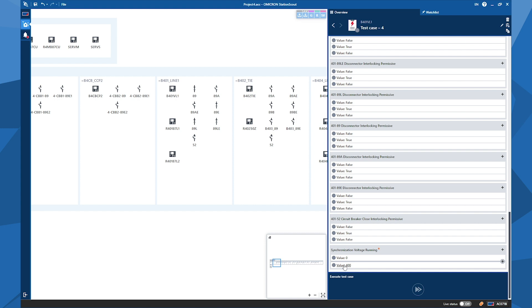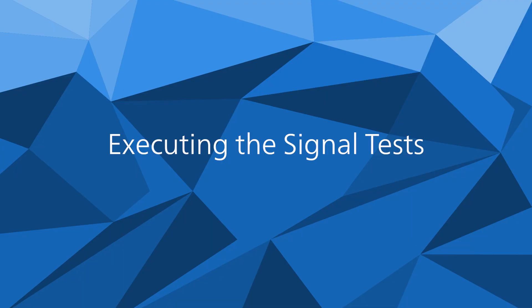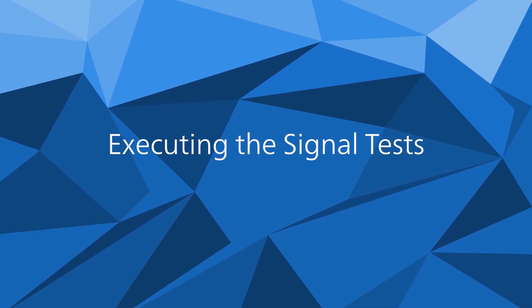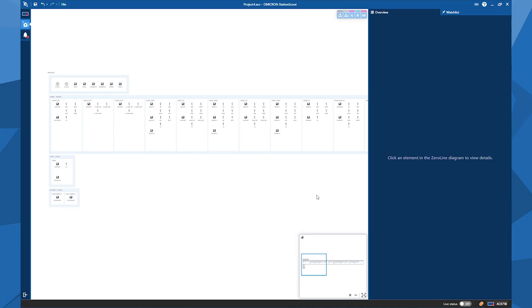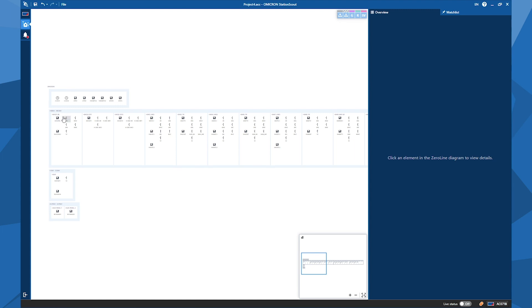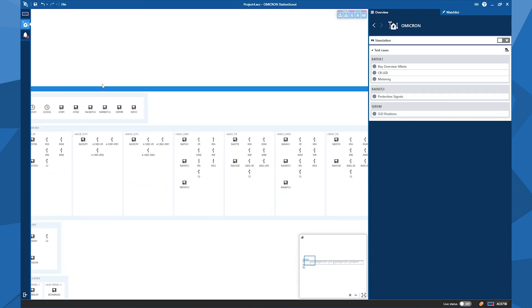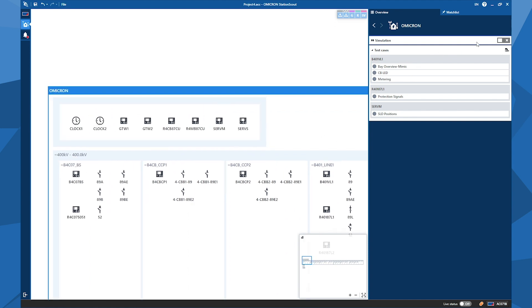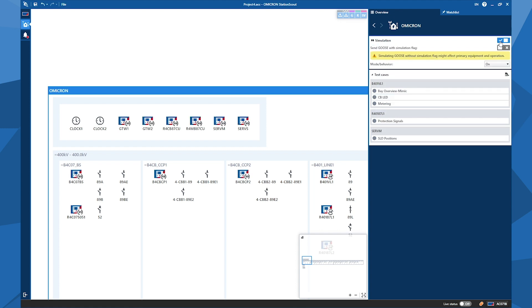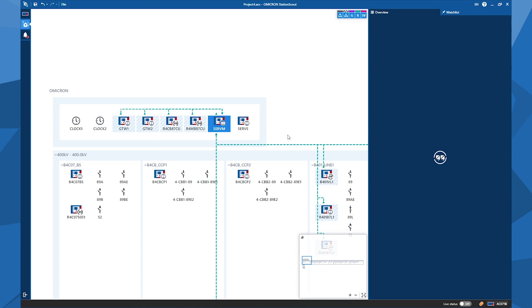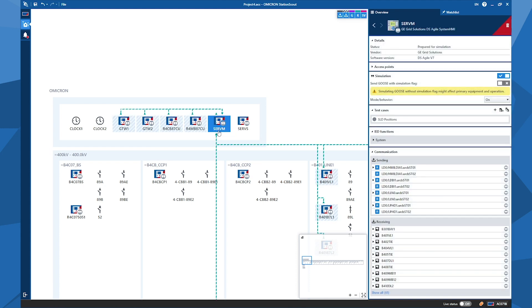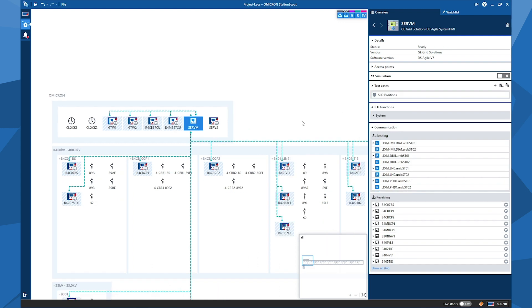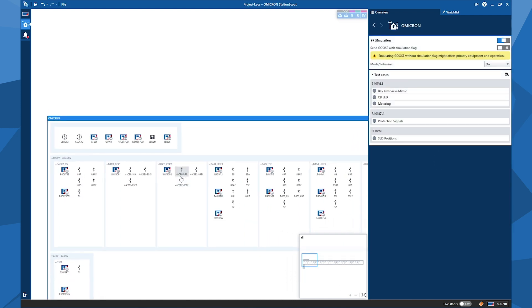So okay, now we can go online and run the test sets. Now we can start going online and start the simulation and run the test cases that are already prepared. So for starting the simulation in this system, basically I can click on the substation, the entire substation, and on the right-hand side I have the simulation slider. I will click on it to switch it to enabled, and now I have the opportunity to deselect some of the IEDs which I don't want to simulate. In this case, I don't want to simulate the HMI, which is the main server here. I deselect this one, and other than that, I don't need to deselect any IED. So this means that all the IEDs here have been prepared for simulation.